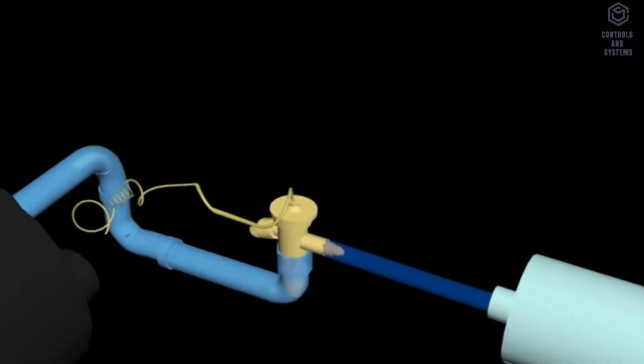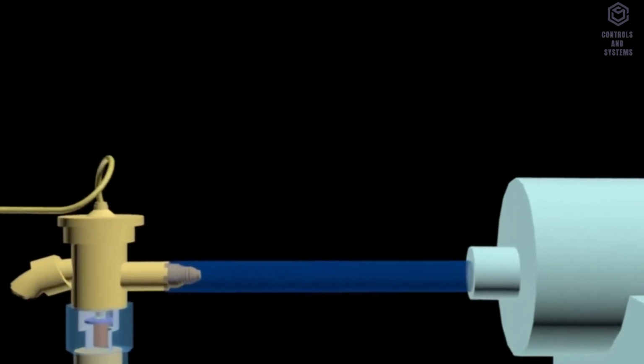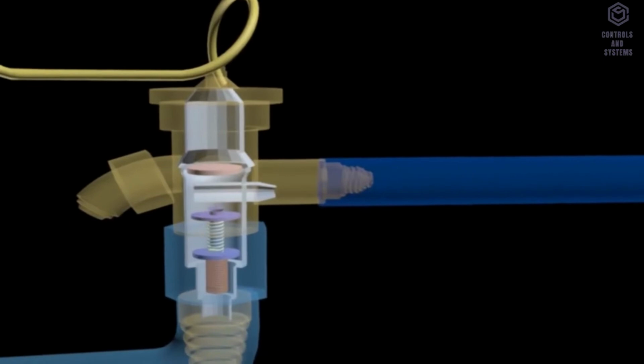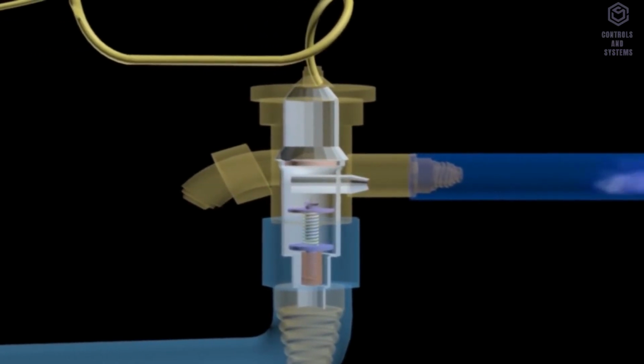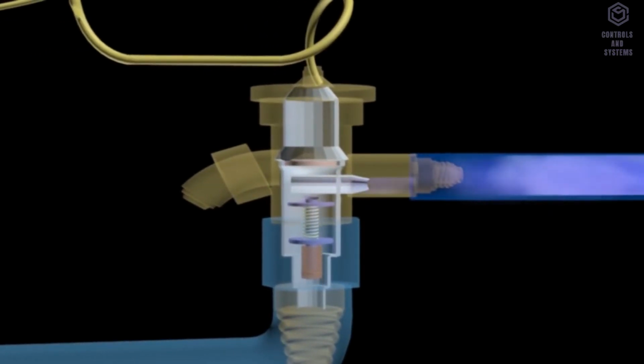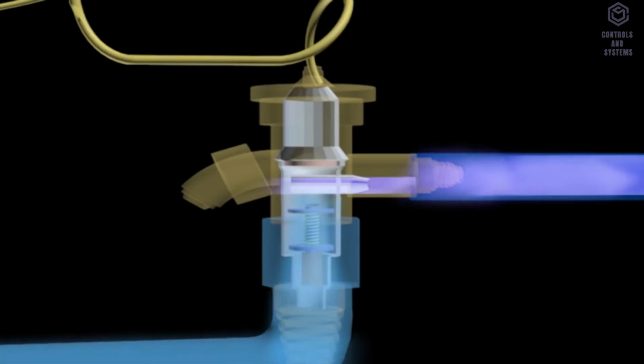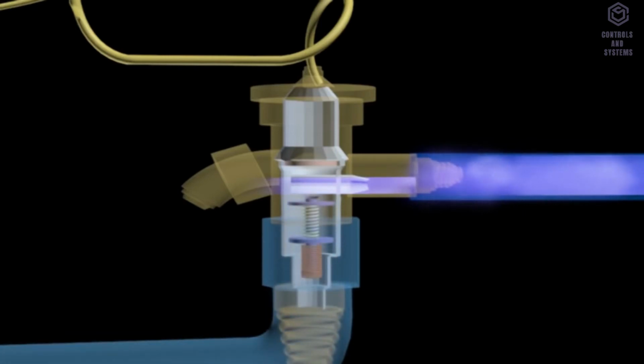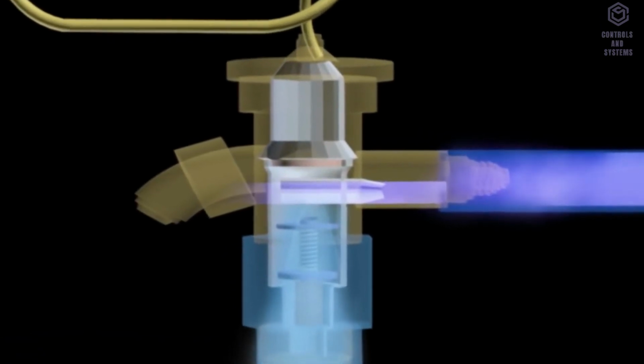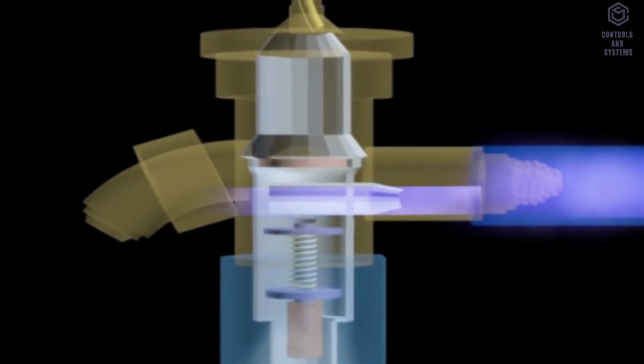Expansion valve. The expansion valve serves to reduce the pressure and control the flow of refrigerant going into the evaporator. When the pressure of the refrigerant drops drastically, the temperature will also drop dramatically, to lower than the chilled water temperature. In a centralized system, the thermal expansion valve type of expansion device is used.